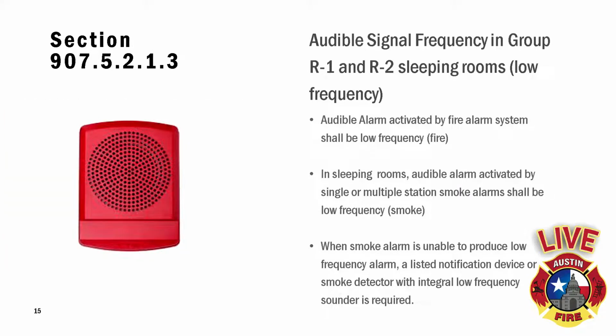A provision that we've required for a while and had some additional and clarifying language is going to be the low frequency sounder bases. And what this section really is requiring is an additional device, essentially. When you had the single or multiple station devices, you could get a sounder base, or if you can't get a sounder base, then a separate system or device is going to be required, and that's going to have to connect to the fire alarm system.